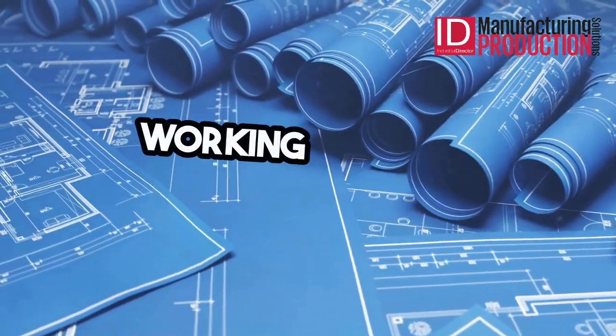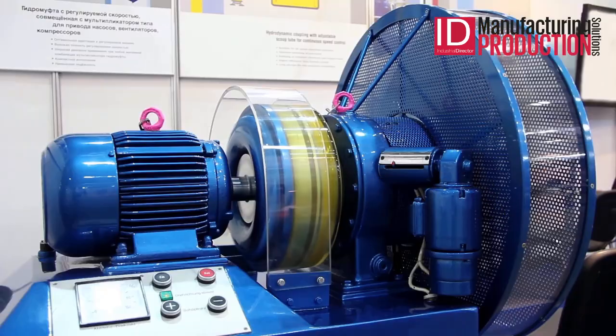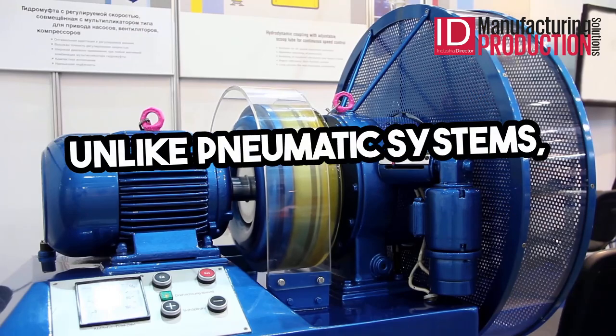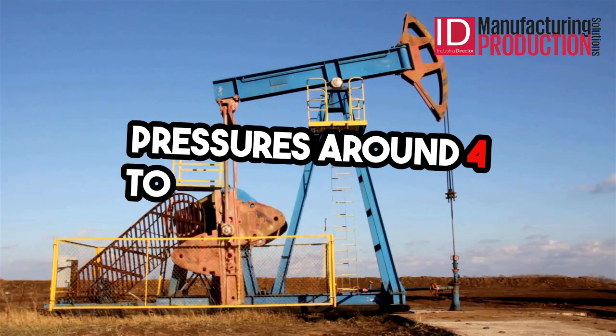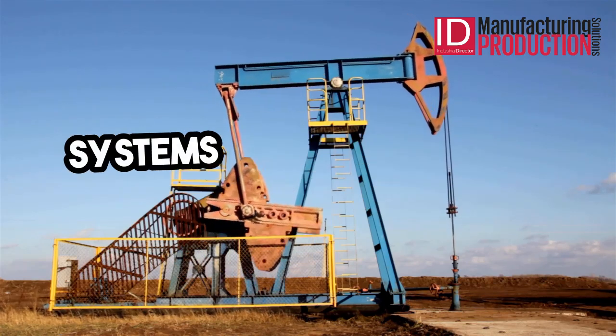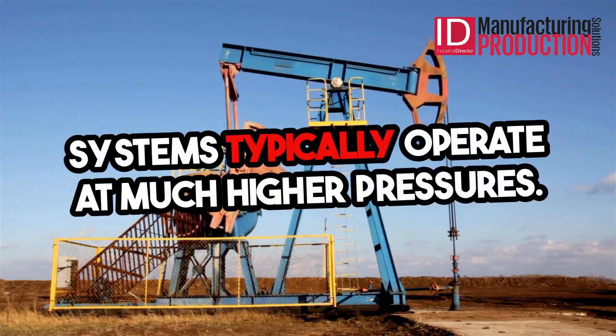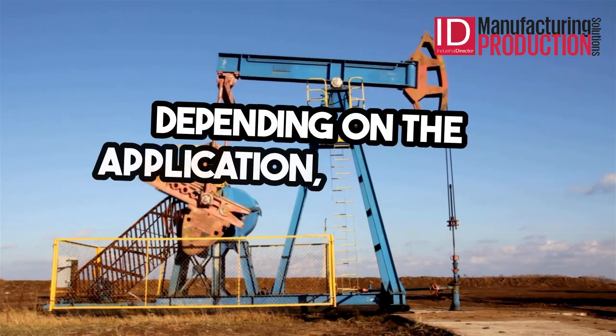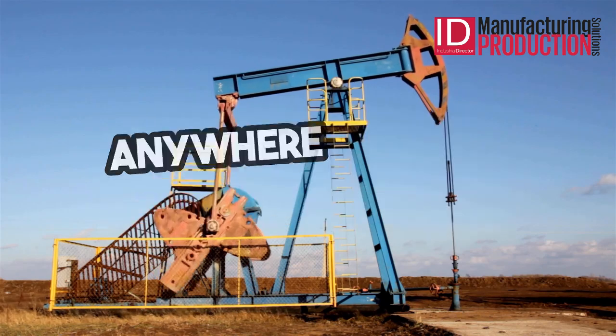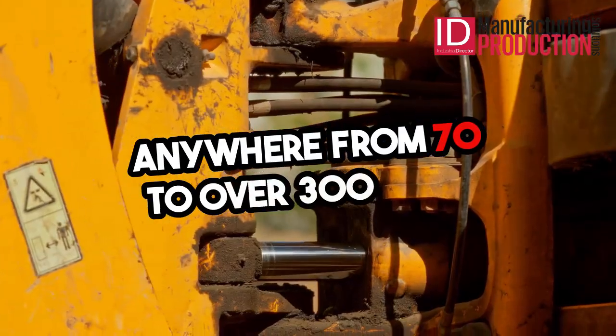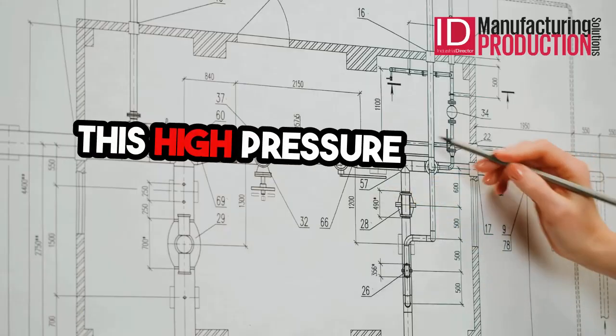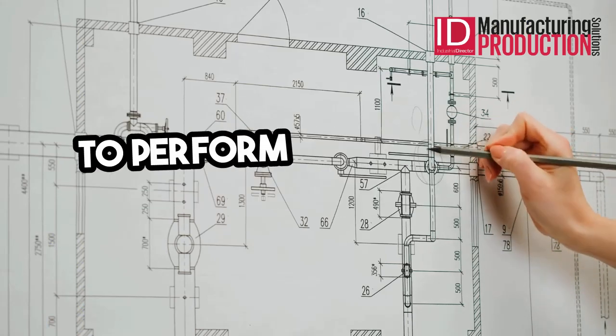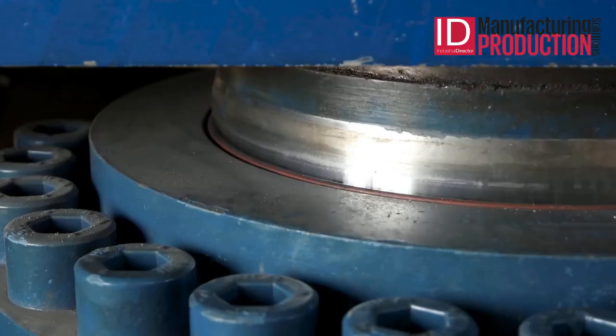Now, let's talk about the working pressure in hydraulic systems. Unlike pneumatic systems, where we often see pressures around 4 to 5 bars, hydraulic systems typically operate at much higher pressures. Depending on the application, hydraulic systems can function anywhere from 70 to over 300 bars. This high pressure is what allows hydraulic systems to perform heavy lifting and precise movements.